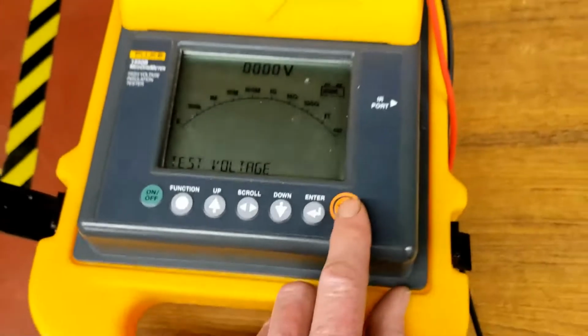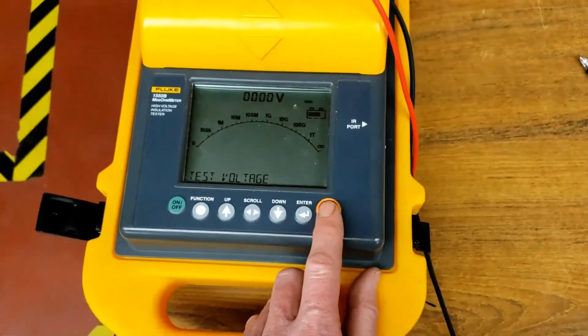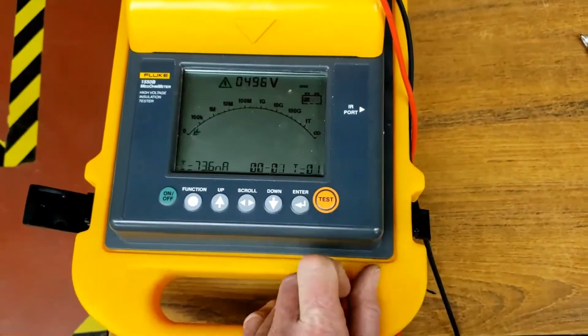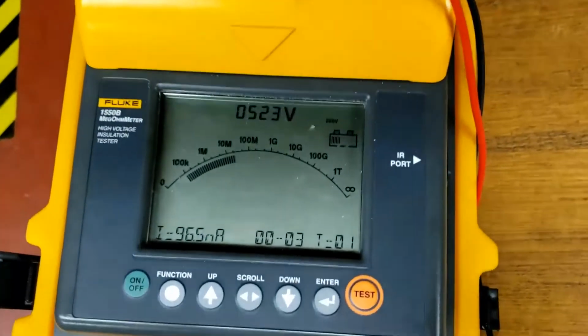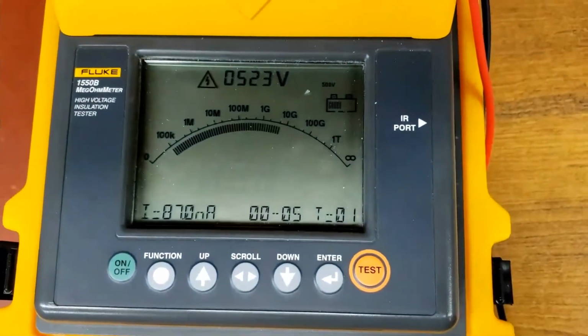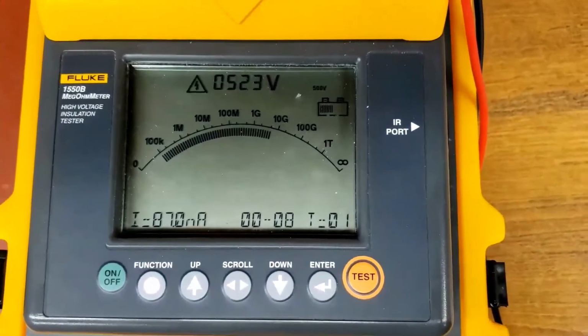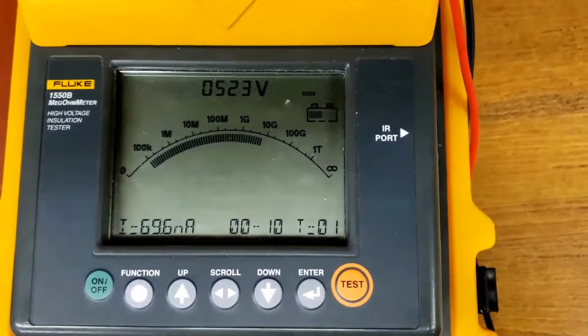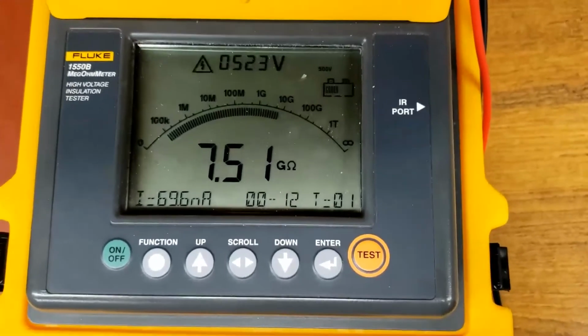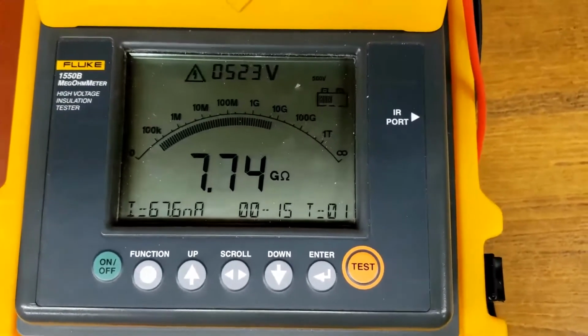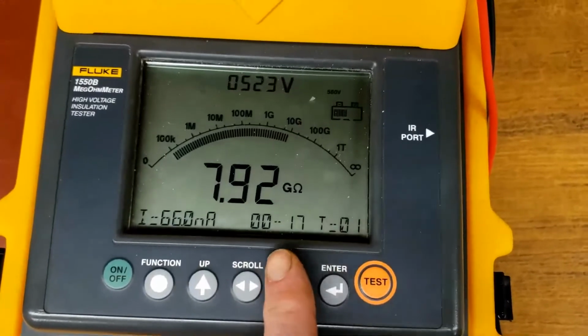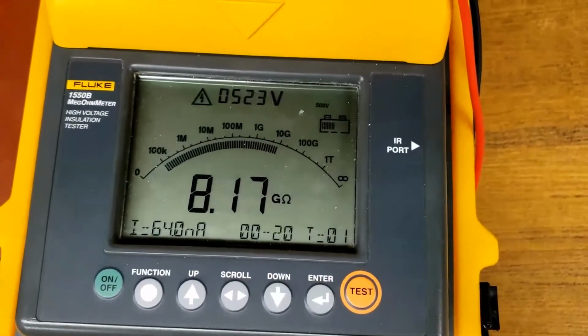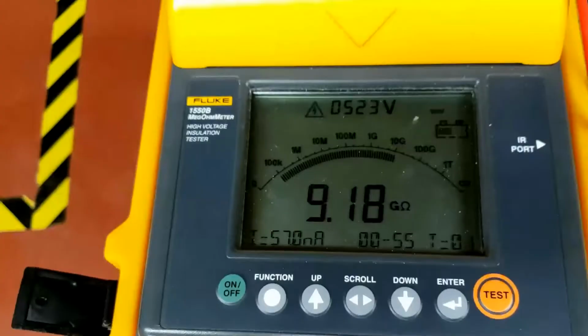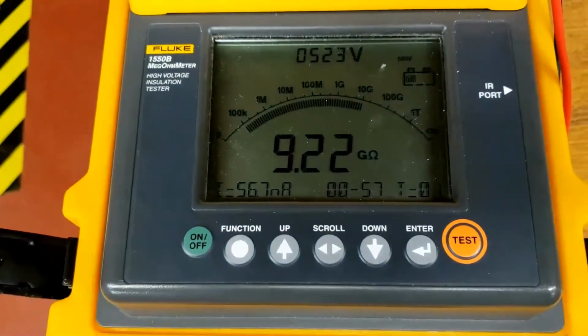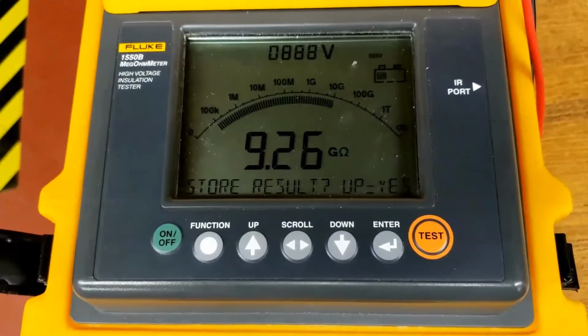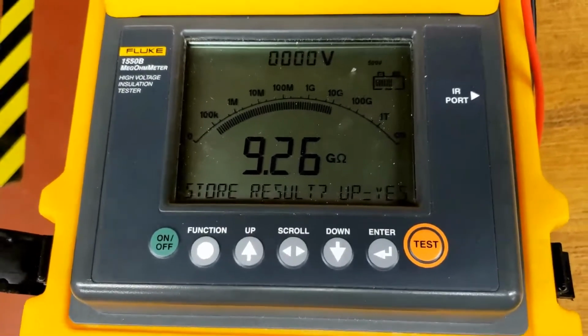You have to push and hold the test button, and it'll start to test. And you can see the current flowing in the bottom left. You can see the apparent resistance showing up as giga-ohms, and then it'll start doing the reading, and our timer is going right here. So when this is finished, it'll give us a reading. So it's just about finished, and it's stabilized at about 9 gigohms.